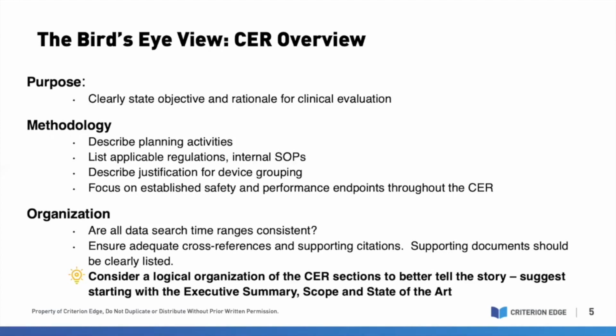Is methodology well documented and thorough throughout the CER? For example, are your planning activities described? Are all applicable regulations and internal SOPs listed? Is a justification for the device grouping clearly outlined?